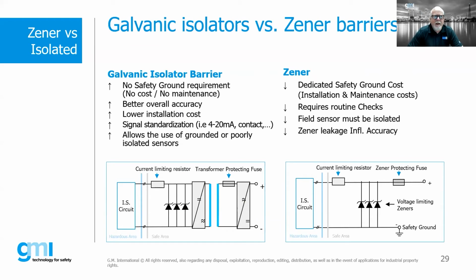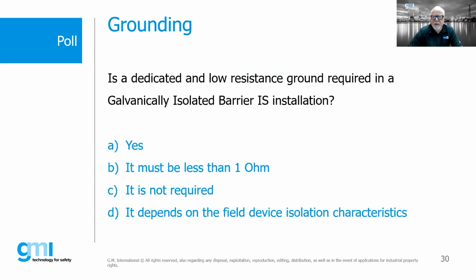So just to summarize a little bit here, galvanically isolated, again, no safety ground requirement. Better overall accuracy, lower installation cost, right? Signal standardization. Again, it does allow the use of grounded or poorly isolated sensors. The Zener has a dedicated safety ground, right? There are those routine checks. The field sensor must be isolated. There is some accuracy impact with regards to Zener leakage, if you will. So, there are pros and cons of each, right? And again, from a pure cost standpoint, galvanically isolated barriers generally are going to cost more than a Zener barrier. But you have to take into account what are the things that I'm trying to do. The total installed cost, usually galvanically isolated is a better way to go. But again, certain applications may make more sense to do it one way or the other.